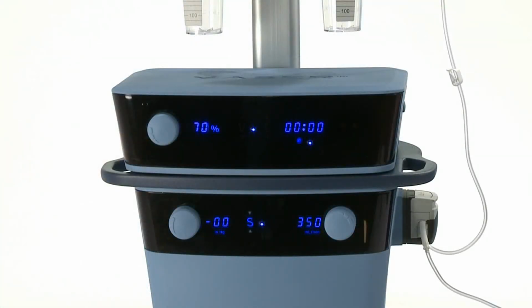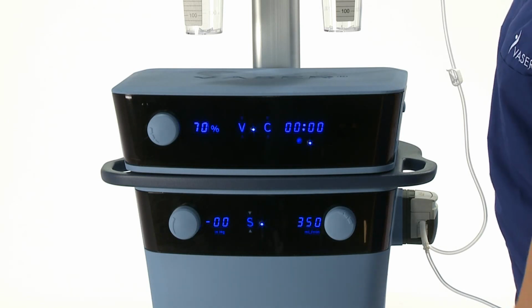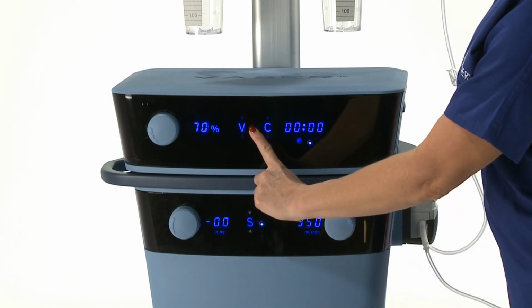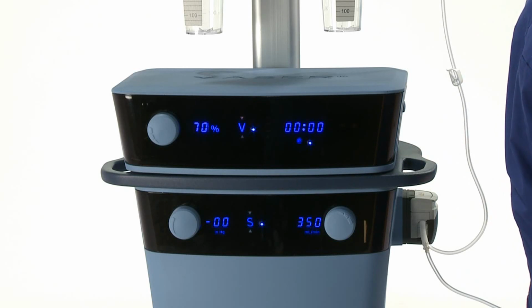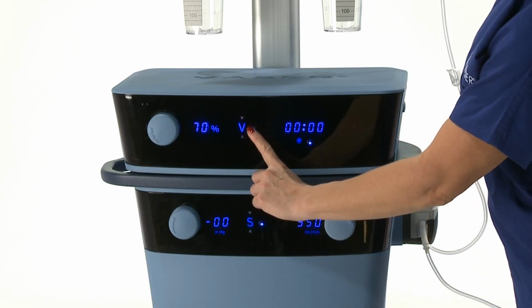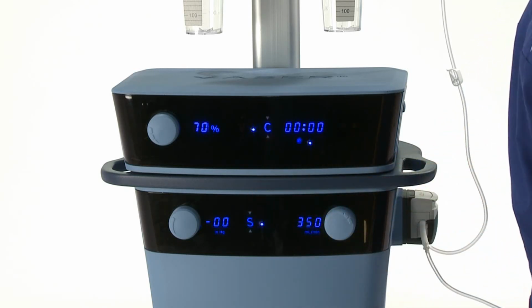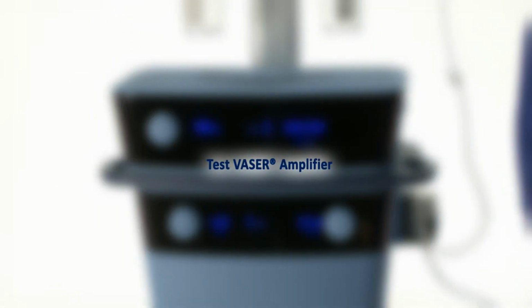Upon initial power on, the Vaser amplifier should always default to a standby operating mode indicated by a flashing V and C. To place the amplifier into a working mode, toggle the mode switch to select either V or C, Vaser or continuous mode, respectively. Next, you will need to test the Vaser amplifier.